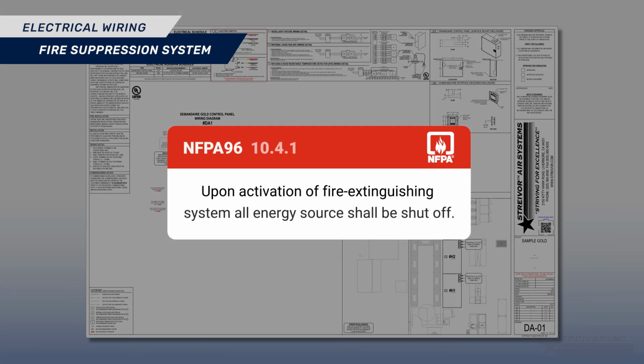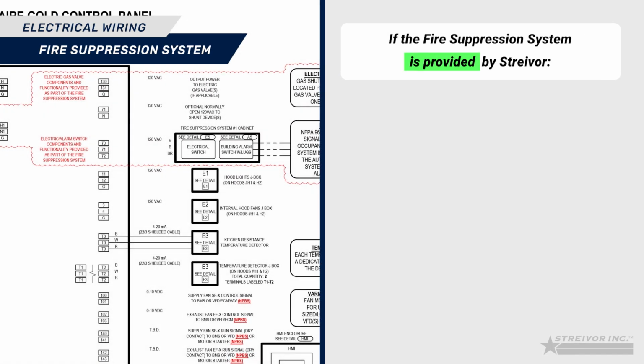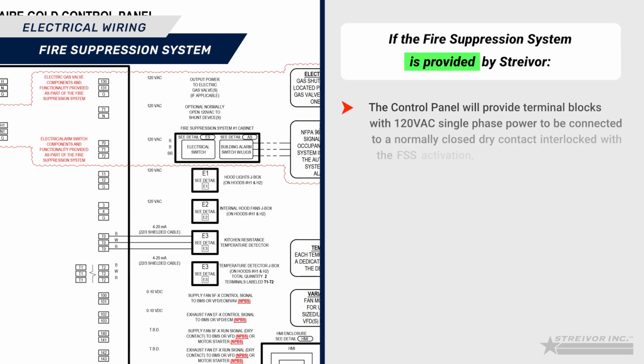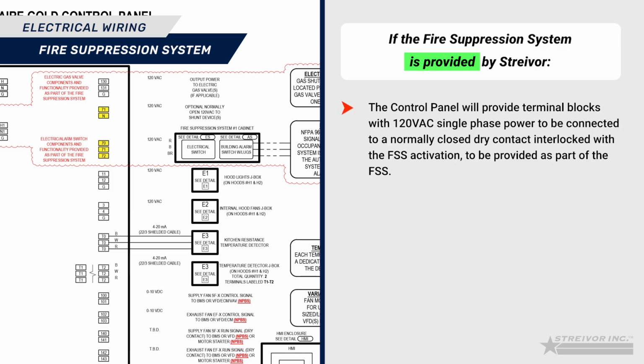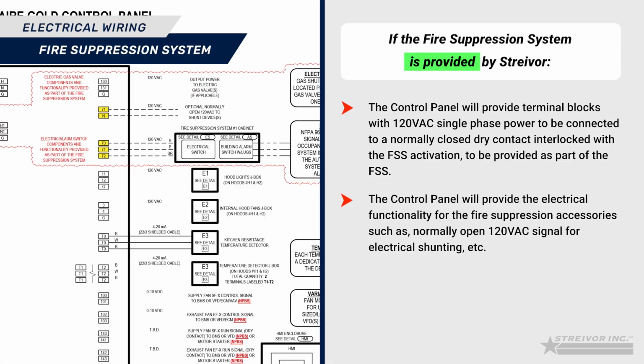The control panel is engineered to comply with NFPA 96 Section 10.4.1. If the fire suppression system is provided by Streivor, the control panel will provide terminal blocks with 120 VAC single-phase power to be connected to a normally closed dry contact interlocked with the FSS activation to be provided as part of the FSS. The control panel will provide the electrical functionality for the fire suppression accessories such as normally open 120 VAC signal for electrical shunting, etc.